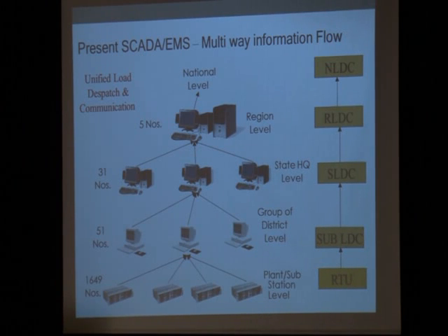People are sitting at what are called dispatch centers, load dispatch centers, or communication centers, and these are hierarchical in nature. At the bottom level we have substation or plant level sensor information—I'll explain the sensors in a second. They send information to a district level decision-making authority called the LDC, Load Dispatch Center, or sub-LDC. These collect information and send it to state level decision makers, and finally to the national level.